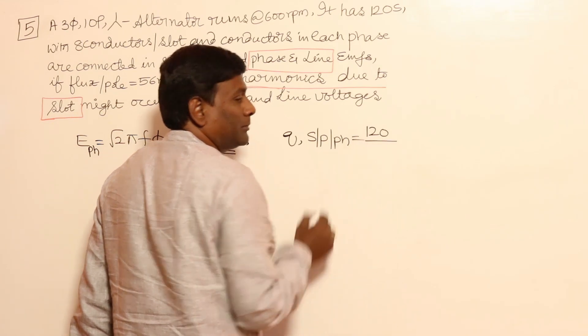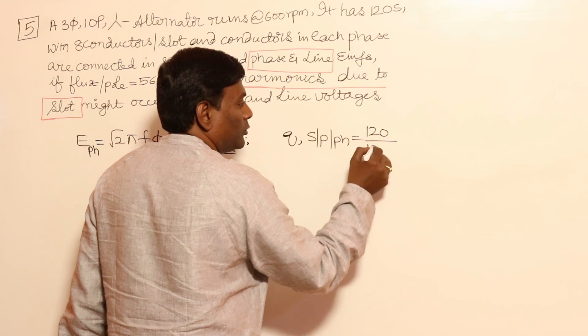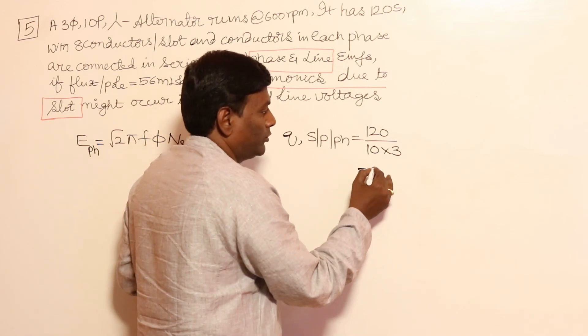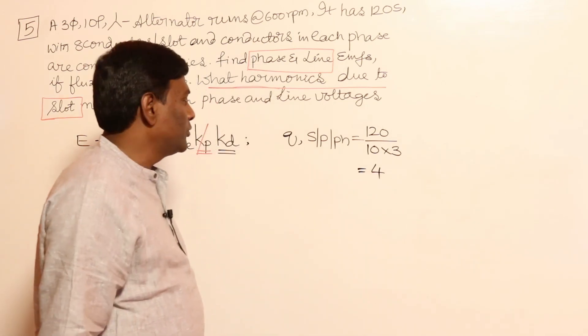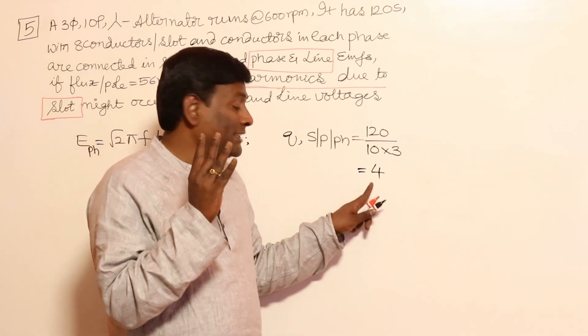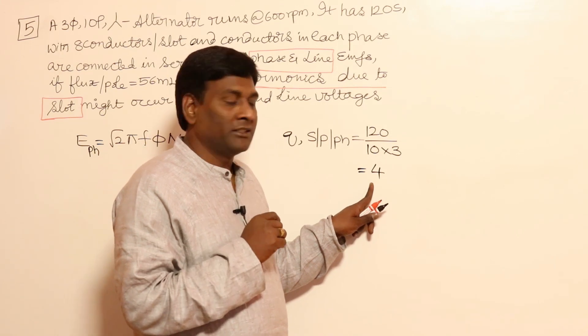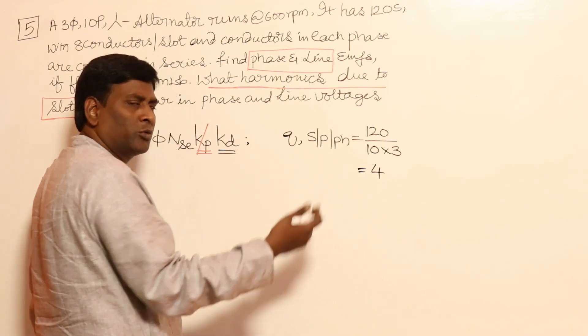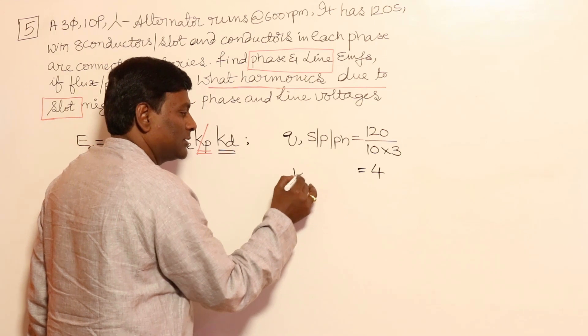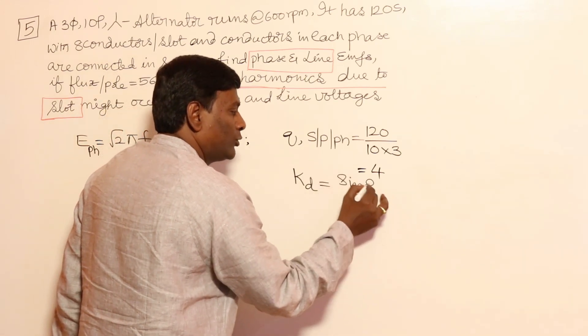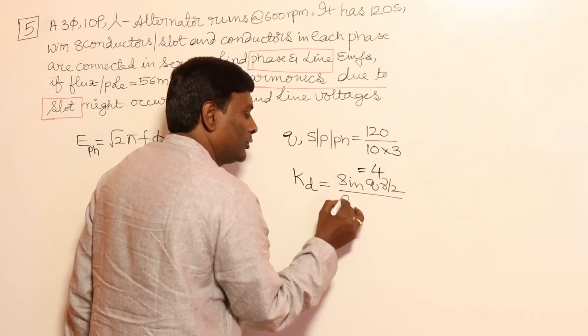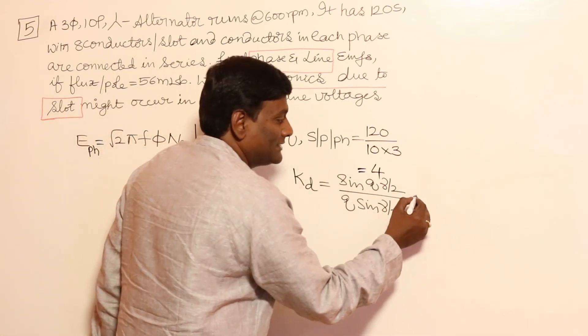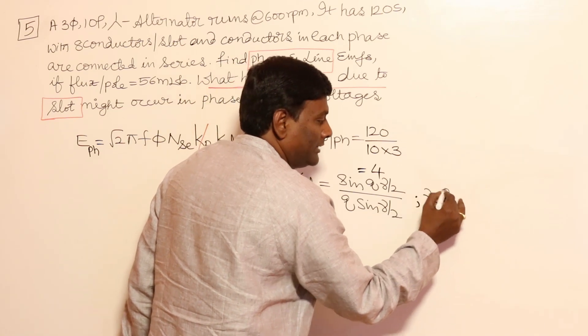q = slots per pole per phase = 120 slots divided by poles (10) and number of phases (3), which equals 4 slots per pole per phase. So per pole, 4 slots are available for distribution. Now, distribution factor = sin(q · γ/2) / (q · sin(γ/2)), where q is slots per pole per phase and γ is the slot angle, which we have to calculate.